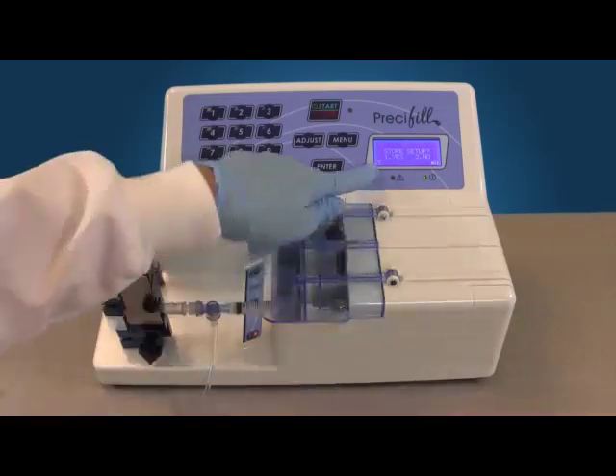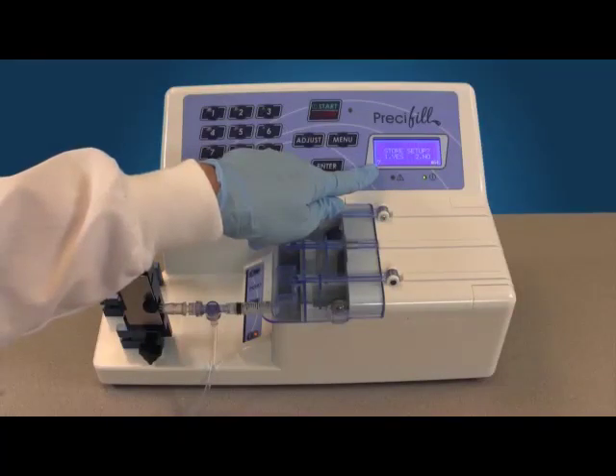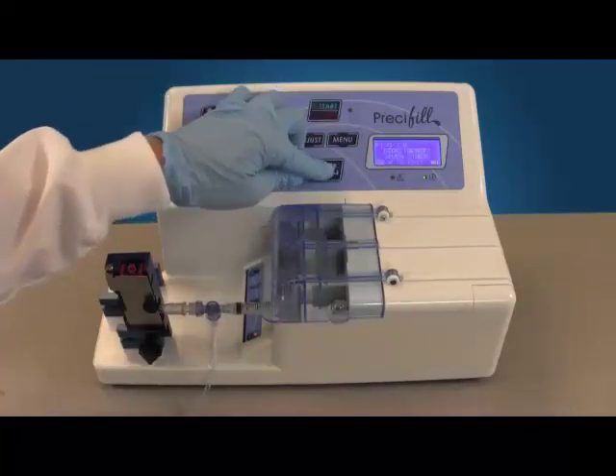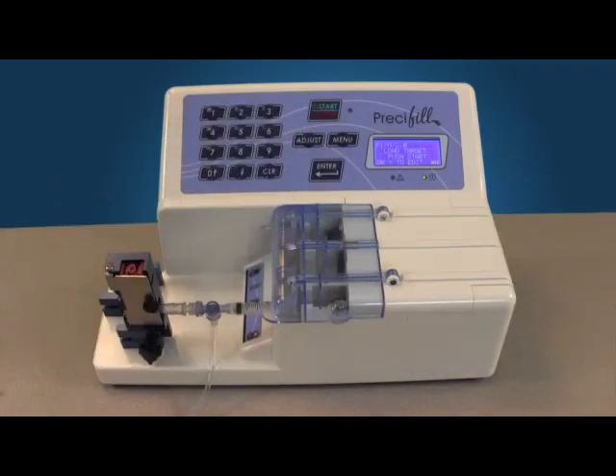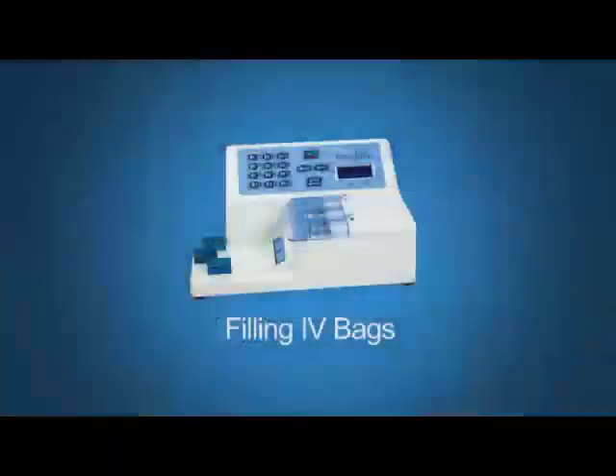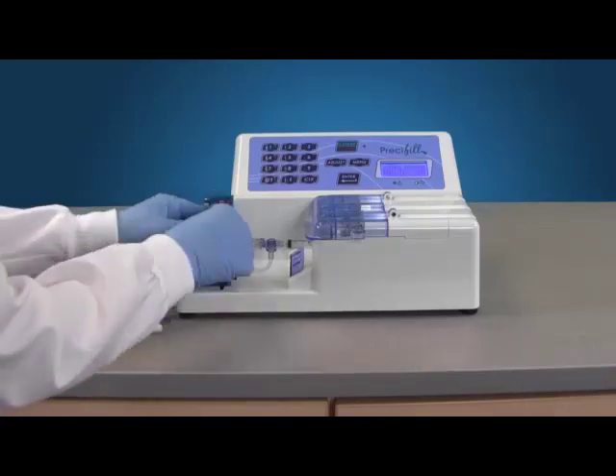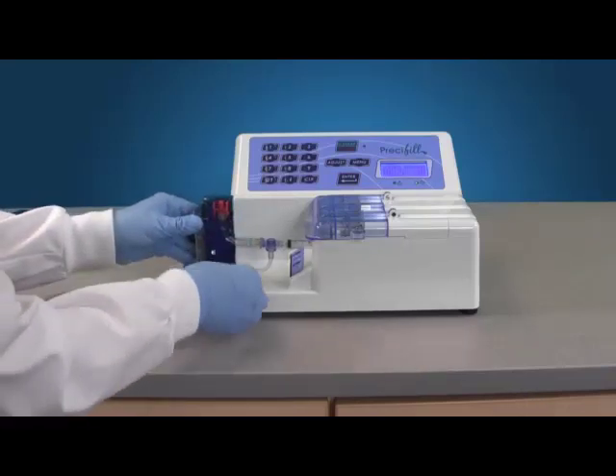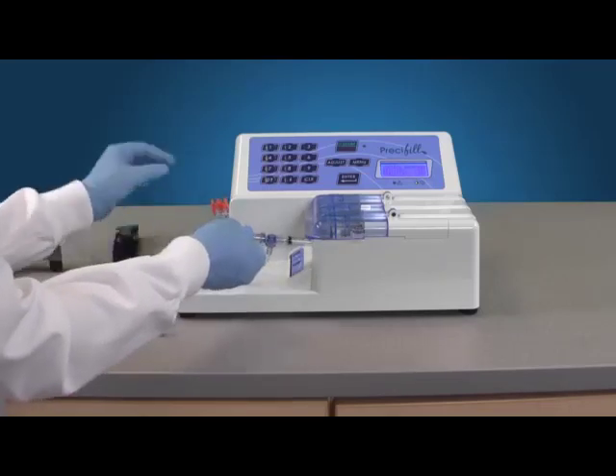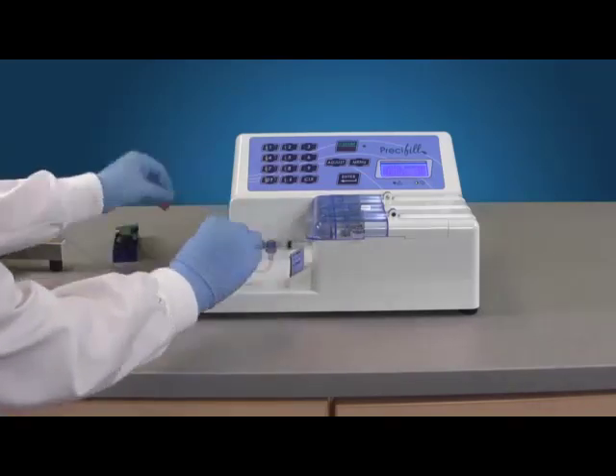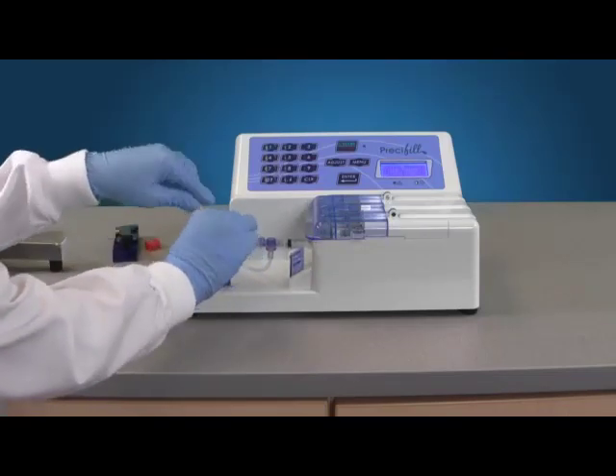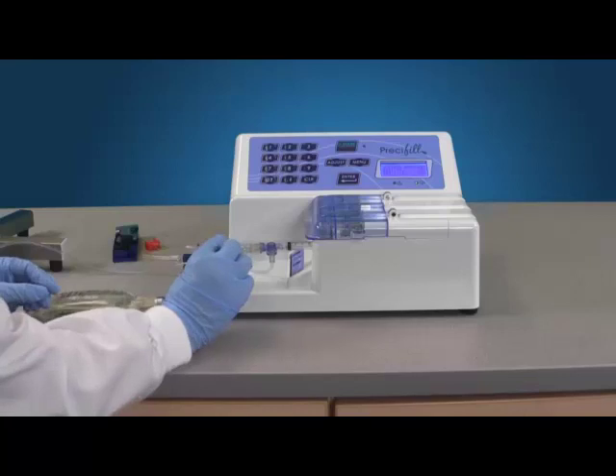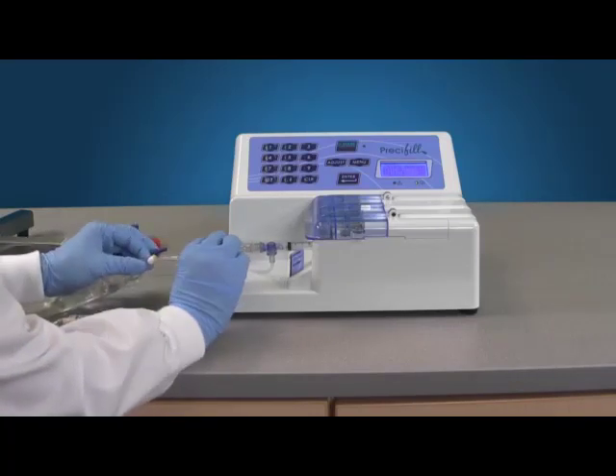Calibration is stored automatically. The next screen reads Store Setup. Choose 1 for yes or 2 for no. Choosing Store Setup is for the overall program, not the calibration. Your pump is now primed, calibrated, and ready for repeated filling. To fill IV bags, remove the block holder and adapter from the tubing. Attach a needle and insert the needle into the IV bag and start filling.